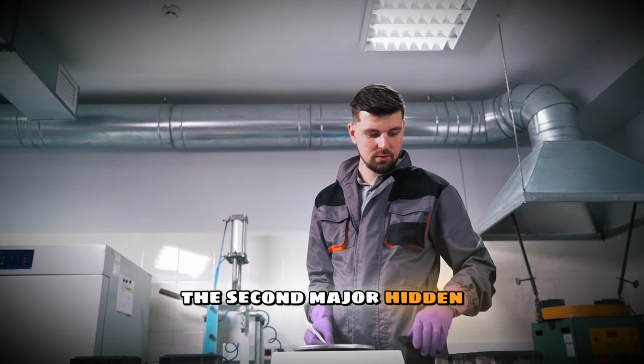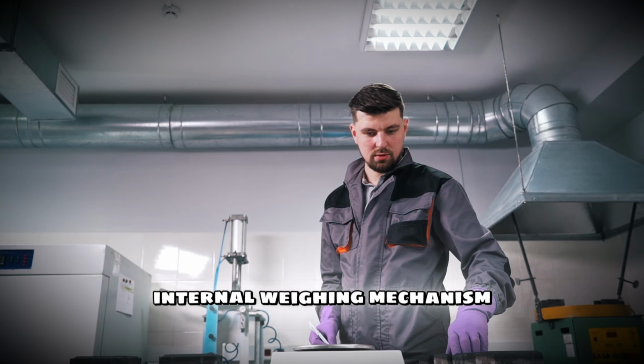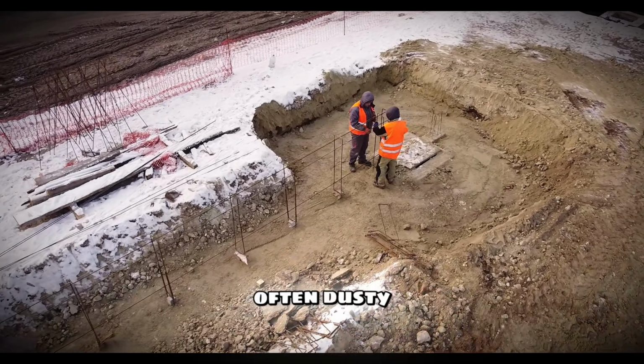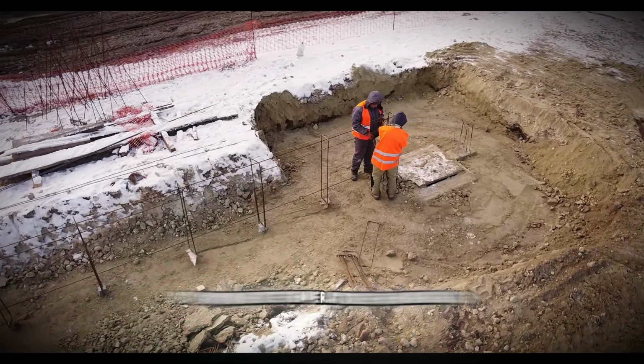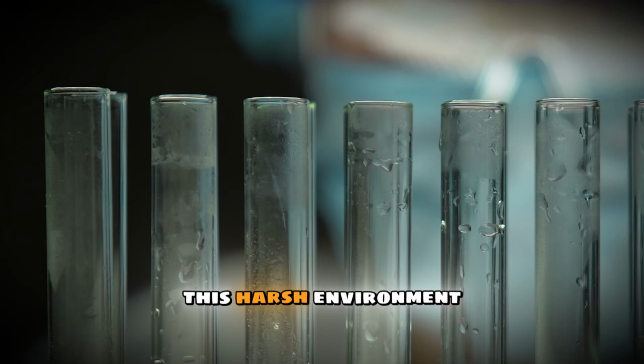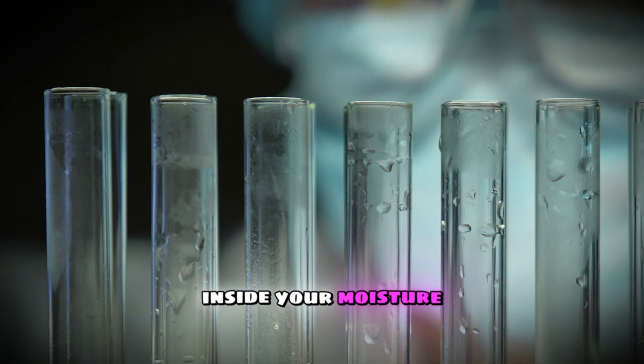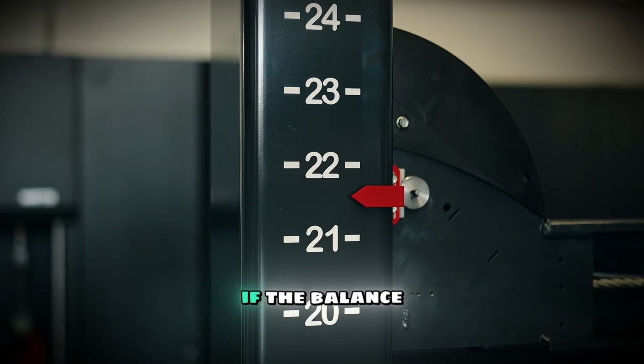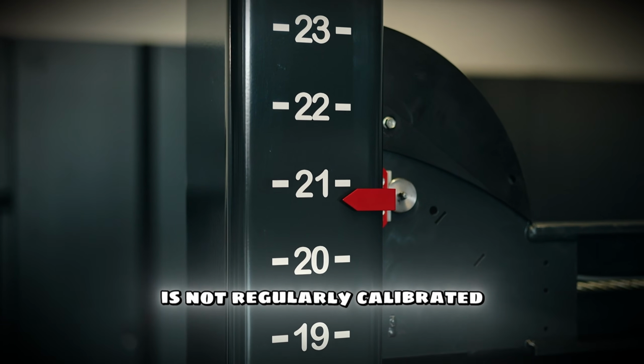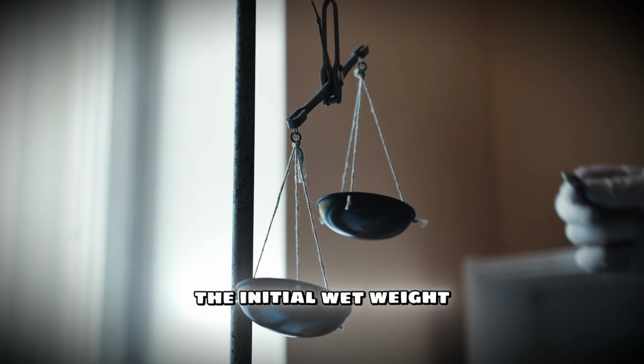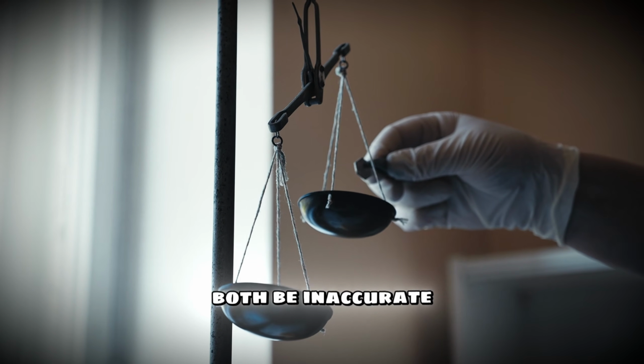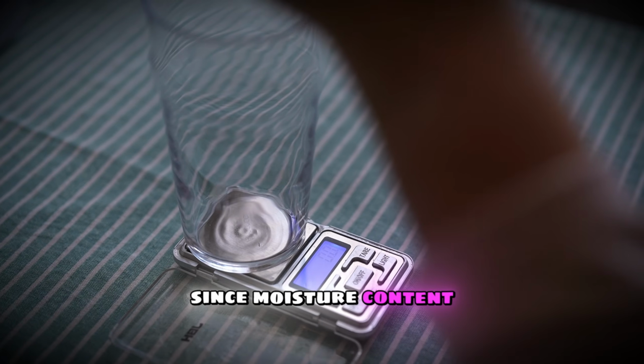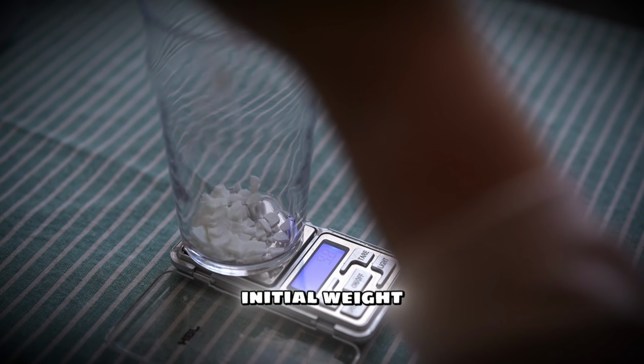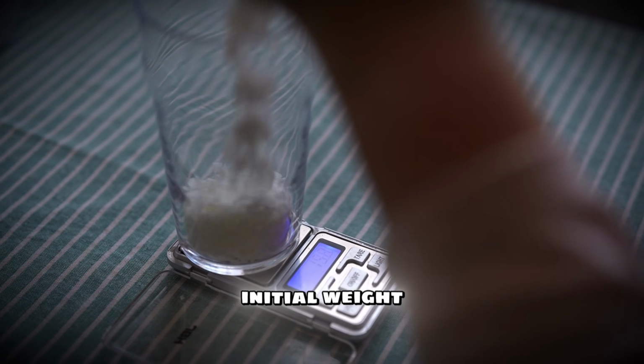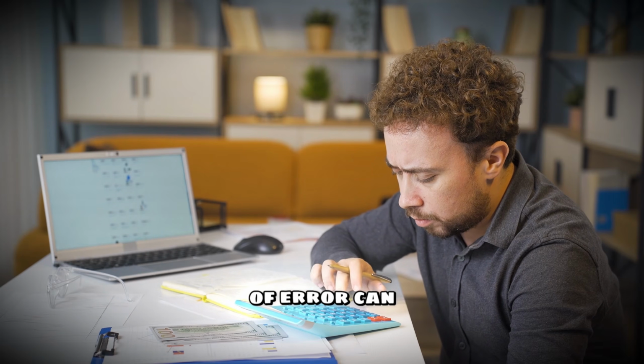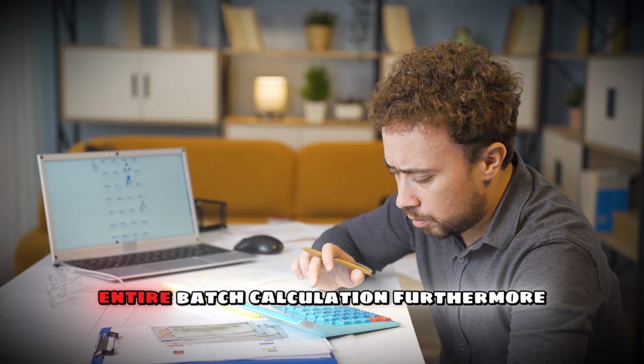The second major hidden error involves the internal weighing mechanism. Construction laboratories are often dusty, vibrating, and subject to wide temperature swings. This harsh environment can cause the load cell inside your moisture analyzer to drift. If the balance is not regularly calibrated using certified check weights, the initial wet weight and the final dry weight will both be inaccurate. Since moisture content is a strict mathematical ratio of initial weight minus final weight divided by the initial weight, even a fraction of a gram of error can throw off your entire batch calculation.